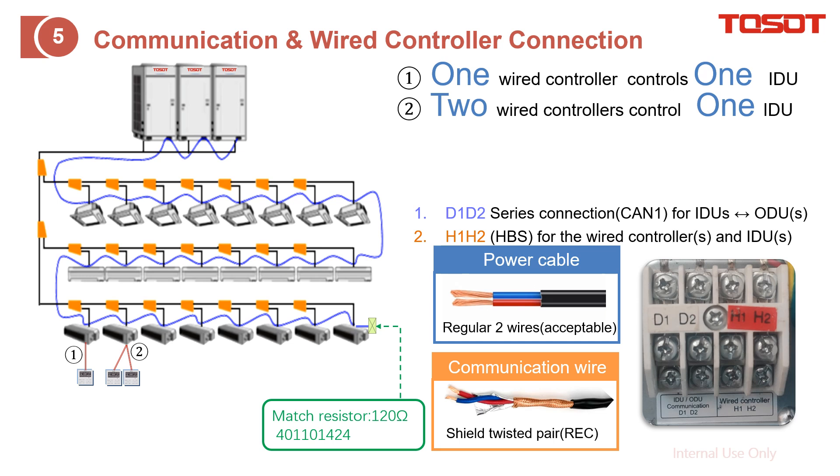How to do the wiring: from this diagram, you can find that the black color line is the power cable — it just connects the outdoor units and the indoor units. And this blue wire is the communication cable, connected on D1 and D2. It is connected from top to tail. We also recommend that at the last indoor unit, you wire the match resistor.